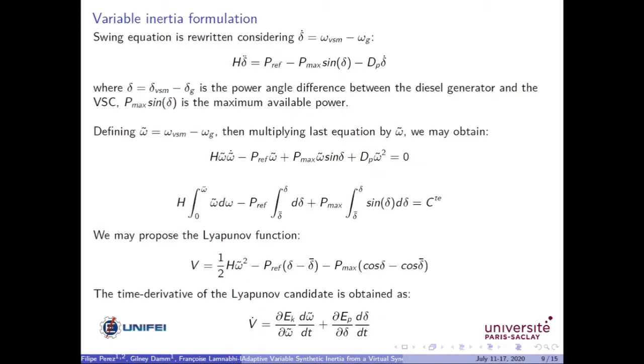To formalize this idea, we can conduct a stability analysis where the swing equation is rewritten. Here, delta is the power angle difference between the diesel generator and the VSC. Pmax sin delta is the maximum available power. So, using this single equation, we can propose a Lyapunov function where we multiply the swing equation by omega tilde, and then we integrate them, and we result with the proposed Lyapunov equation. The Lyapunov is based on the energy function of the system.